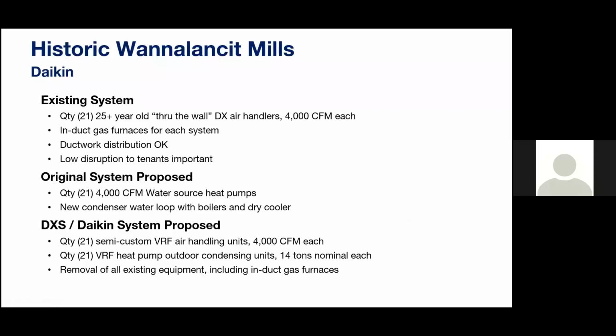So also all of the air handlers were located in mechanical spaces on each floor and would have supply ductwork to each space from there. These actually use the entire mechanical space as a plenum originally, and then just use one large return grill to pull the air back into the return. So with the units being located in the mechanical room, there would be little disruption to tenants in improving the system and coming up with a new system. These also had the condensing section of the air handlers in that mechanical space as well that was ducted to the outside. So you'd have the ductwork for the space air, then the ductwork for the condenser section of the air handler as well, which made the mechanical space pretty packed.